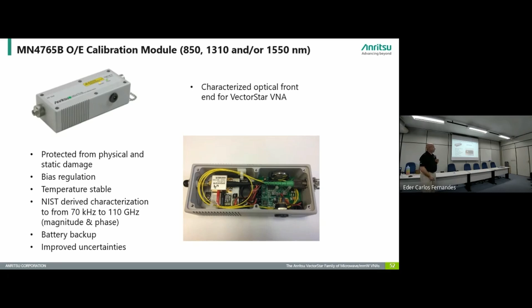The other thing that's interesting here is that if you've ever worked with photodiodes, I'm sure you know that if you apply an optical signal without a bias, you can damage a photodiode very easily. So we built into this module a battery backup, which protects the photodiode in the event that somehow the AC adapter is removed. So this is where the AC adapter goes right here. If that gets removed, then the battery kicks in and keeps the photodiode biased if your optical signal is being applied, because that can pop the photodiode otherwise. So these are very robust. In 20 years, I've never seen one of these fail. They take a lot of handling, but they've never had problems because of all the backup and other things built into them.